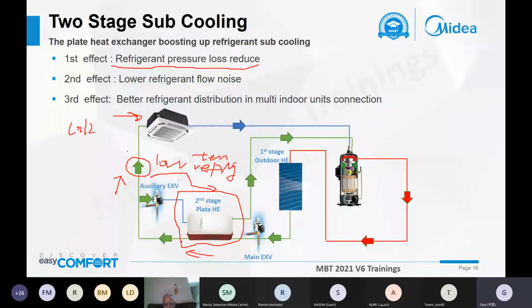And for this part, the refrigerant goes back to the compressors. Compared with the blue line, the temperature here is lower. So we can have a lower discharge temperature of the compressors. That means we can have a wider operating range.